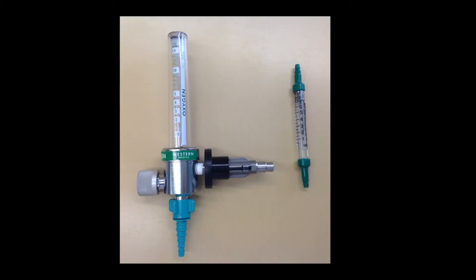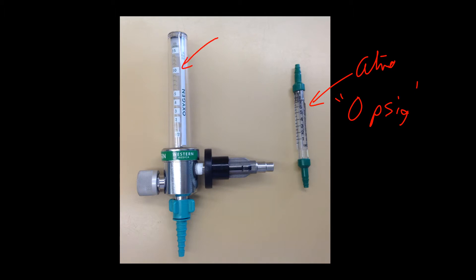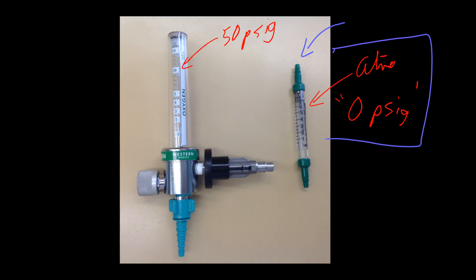Now what we'd like to do is compare the difference between a back pressure compensated flow meter and a non-compensated flow meter. The big difference is that in the non-compensated meter, the pressures inside the Thorpe tube are atmospheric — zero psig — as compared to the compensated one, which operates at 50 psig inside. The key thing to remember is that the compensated meter is unaffected by resistance downstream. When you create resistance downstream, you're changing the dynamics or the atmospheric pressure inside the Thorpe tube, changing the density of the gas and altering how the ball is carried by the supporting gas.